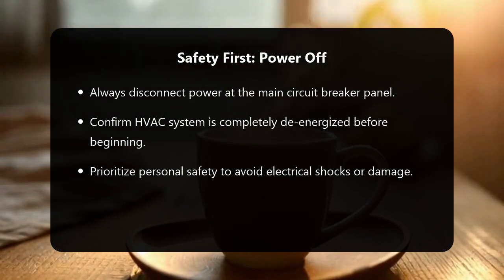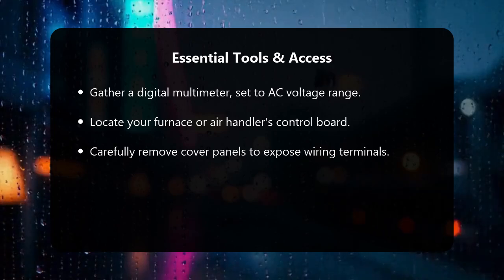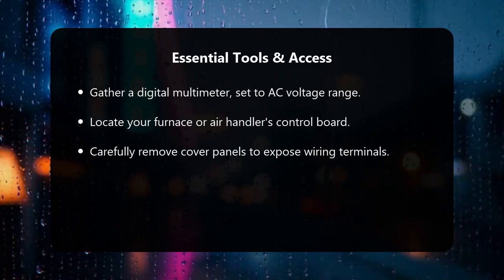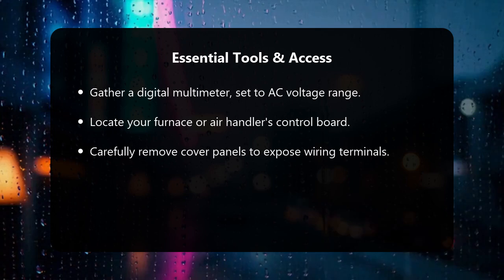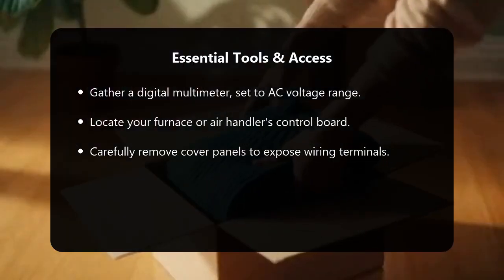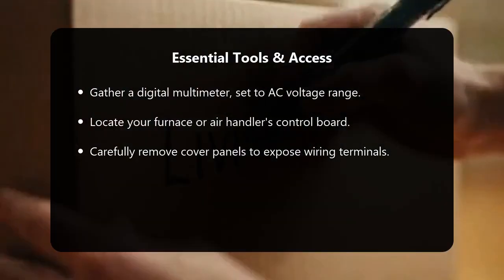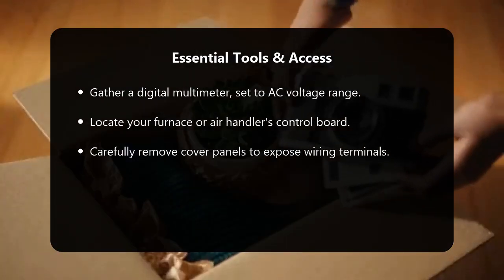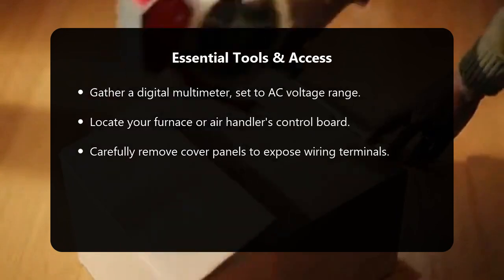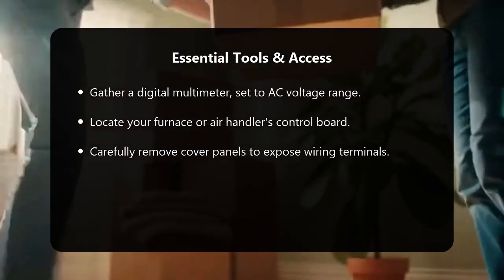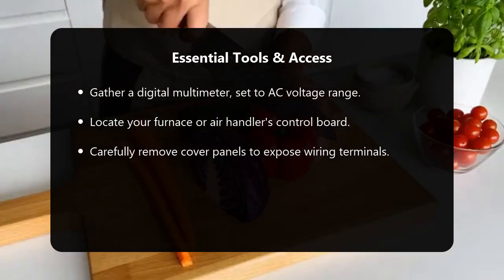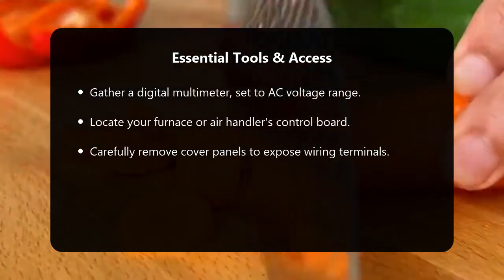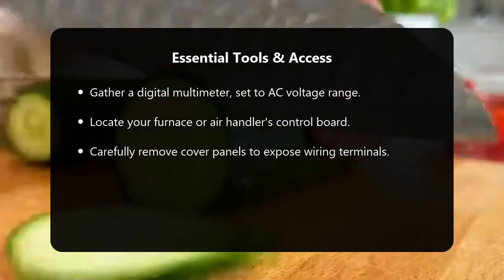You'll primarily need a digital multimeter, which is a versatile electrical testing device. Set your multimeter to measure AC voltage, VAC, typically in the 200V range, or use the auto-ranging feature if available. You might also need a screwdriver to remove any access panels. Next, locate your furnace or air handler. The C-wire connection point is usually found on the control board inside this unit. Carefully remove the cover panel to expose the wiring terminals.